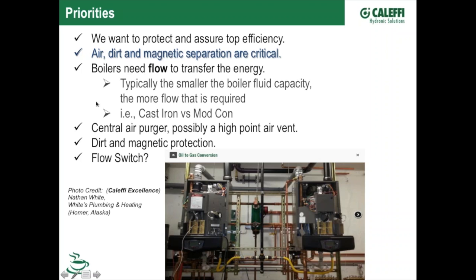And typically what we're seeing is boilers have shrunk over the years: lower fluid capacity, low mass boilers, real thin heat exchangers. We don't have as much wiggle room as we did with the old cast iron boilers, where we had possibly a 1/4 inch thick of metal casting there to give us a little forgiveness as far as abusing that heat exchanger.